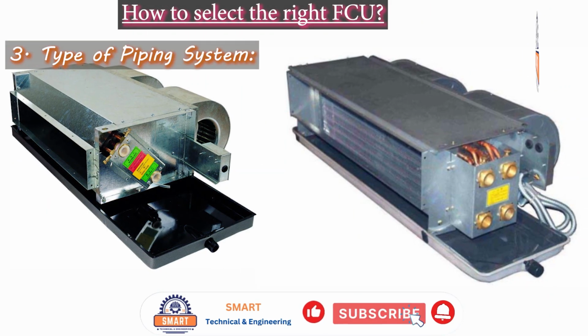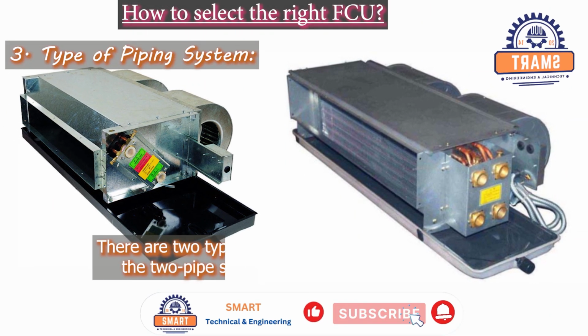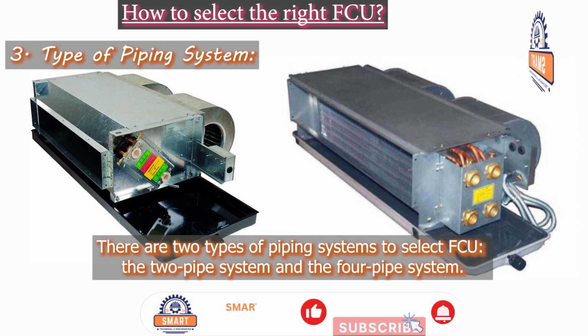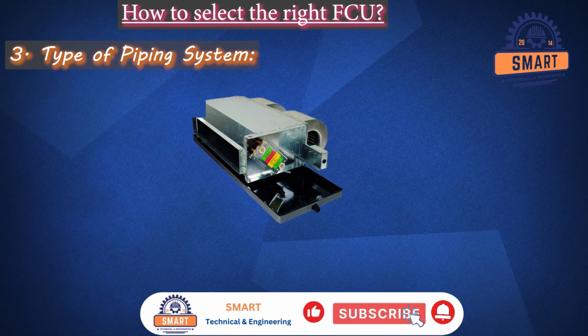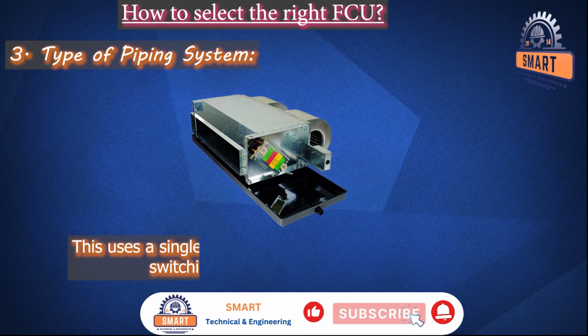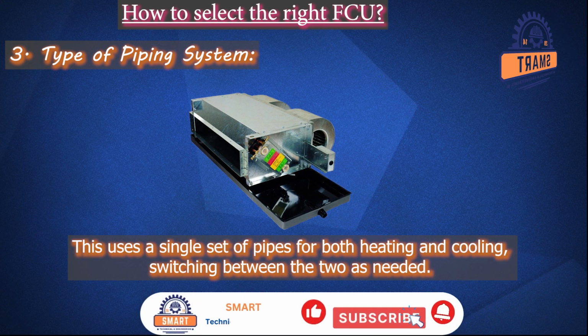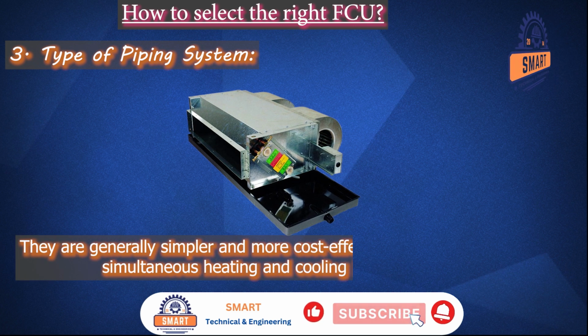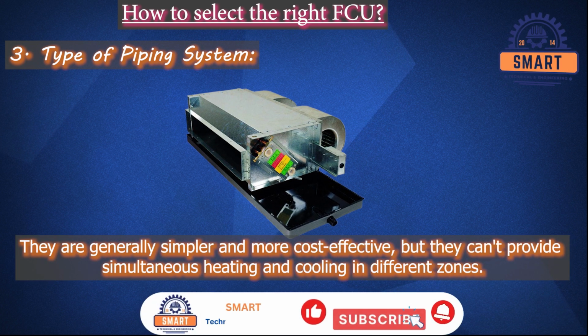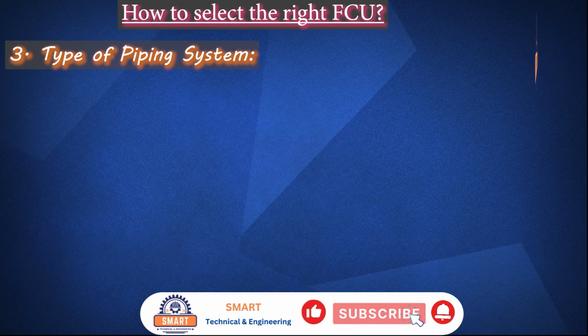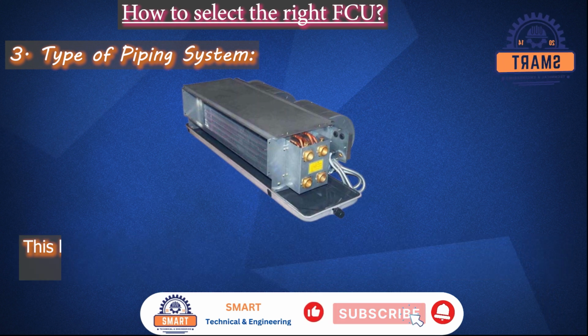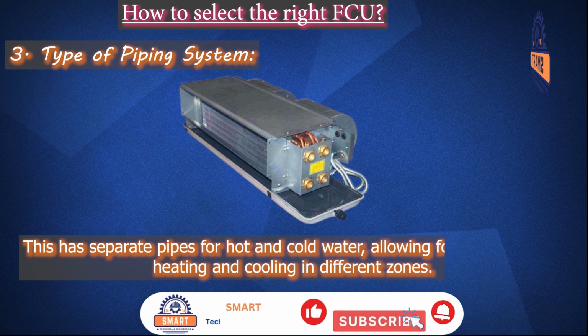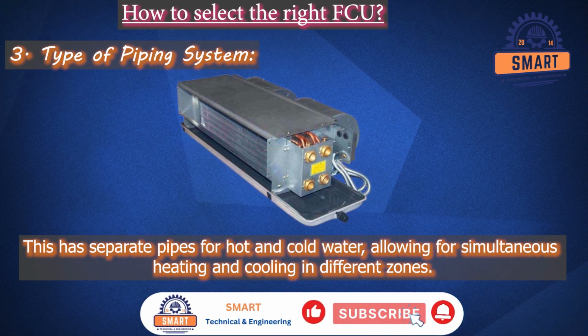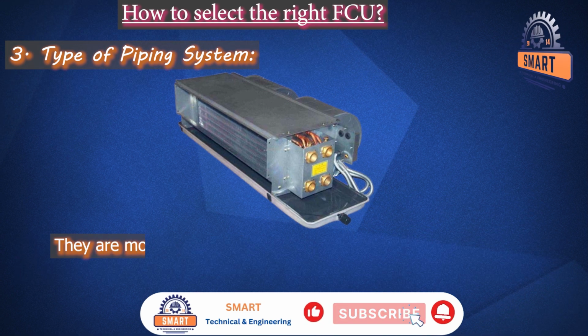3. Type of piping system. There are two types of piping systems to select FCU: the two-pipe system and the four-pipe system. Two-pipe system. This system utilizes a single set of pipes for both heating and cooling, switching between the two as needed. They are generally simpler and more cost-effective, but they can't provide simultaneous heating and cooling in different zones. Four-pipe system. This has separate pipes for hot and cold water, allowing for simultaneous heating and cooling in different zones. They are more complex and expensive but offer more flexibility.